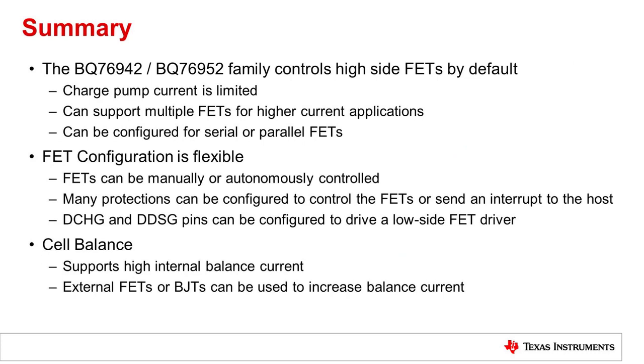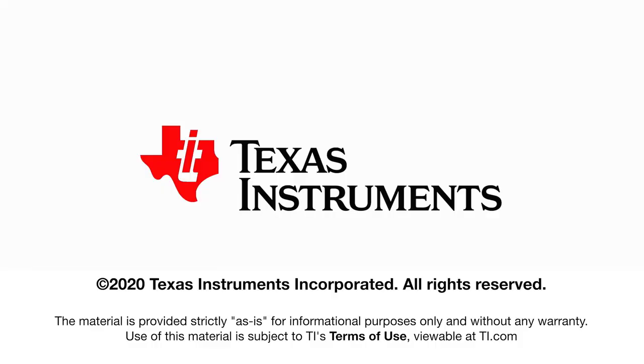In summary, the BQ76942 and BQ76952 family controls high side FETs by default. The charge pump is current limited, so that should be kept in mind. The device can support multiple FETs for high current applications. It can be configured for either serial or parallel FETs. The FET configuration is flexible; the FETs can be controlled manually or autonomously. Many protections can be configured to control the FETs or send an interrupt to the host. The DCHG and DDSG pins can be configured to drive a low side FET driver. For cell balancing, the device supports high internal balance current. External FETs or BJTs can be used to increase the balance current if needed. Thanks for watching. Look out for more information for the BQ76942 and BQ76952 in the product folders linked below. Be sure to click the subscribe to updates button in the product folder to be notified as new helpful materials become available.